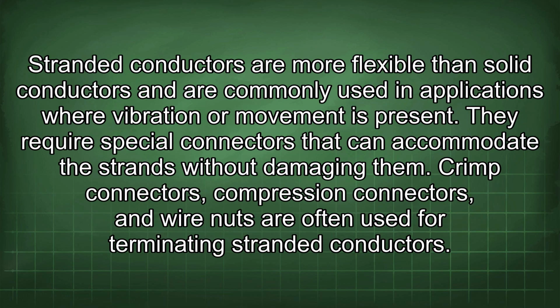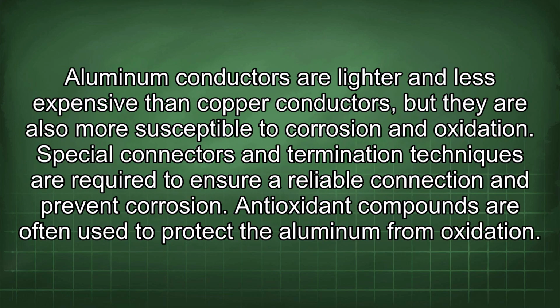Stranded conductors are more flexible than solid conductors and are commonly used in applications where vibration or movement is present. They require special connectors that can accommodate the strands without damaging them. Crimp connectors, compression connectors, and wire nuts are often used for terminating stranded conductors. Aluminum conductors are lighter and less expensive than copper conductors, but they are also more susceptible to corrosion and oxidation. Special connectors and termination techniques are required to ensure a reliable connection and prevent corrosion. Antioxidant compounds are often used to protect the aluminum from oxidation.